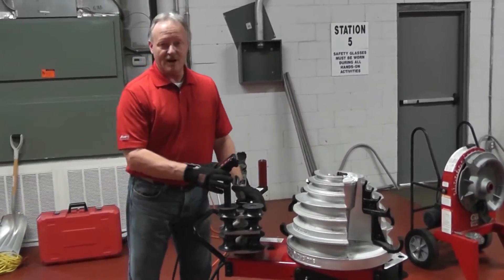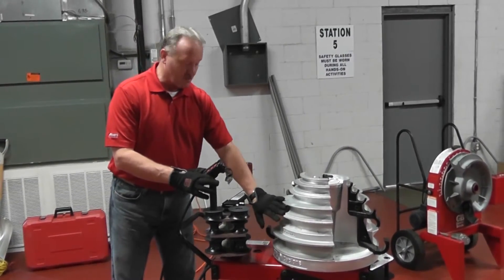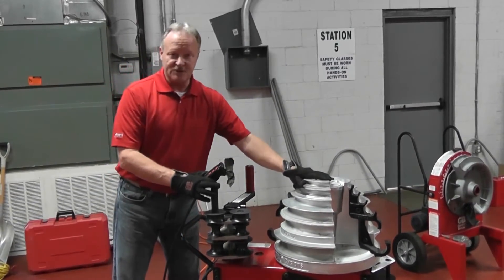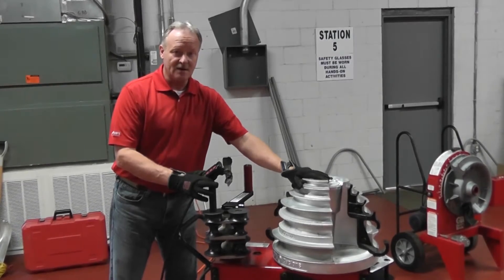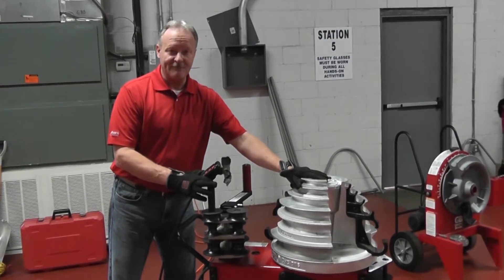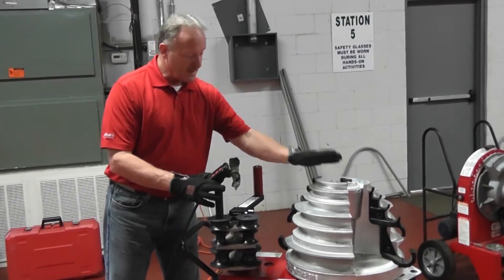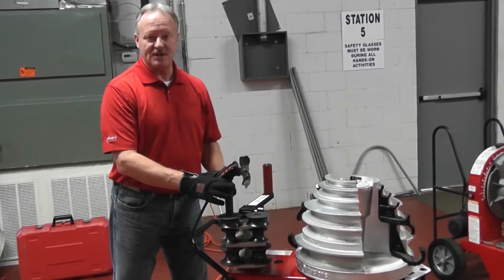The way the unit is set up right now, it's ready to do rigid or IMC because that's the type of shoe — or the side of the shoe — that is actually facing the handles. With this unit, the nice feature is you can do half to two inch EMT, IMC, rigid, and half to one and a half inch PVC rigid aluminum on one shoe with no loose parts. So what I'm going to do is move it from the rigid side over to the two inch EMT.